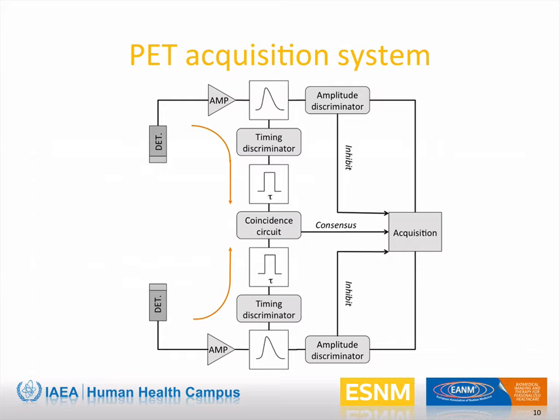In this simplified example, the coincidence circuitry can be a logic AND between the two logic signals that generates a coincidence signal when the two signals have a certain overlap. In this way, a coincidence is accepted when the time difference in the gamma ray arrival is within plus or minus tau. Hence, the effective time coincidence window is actually 2 tau.